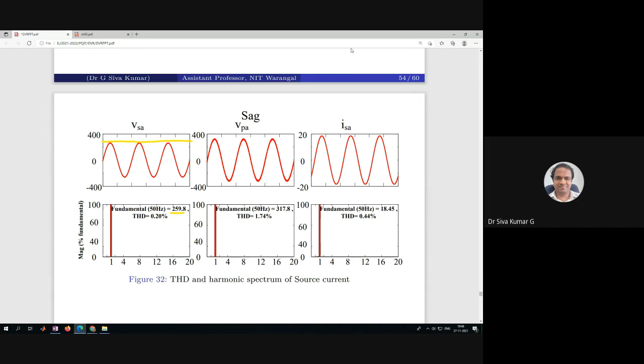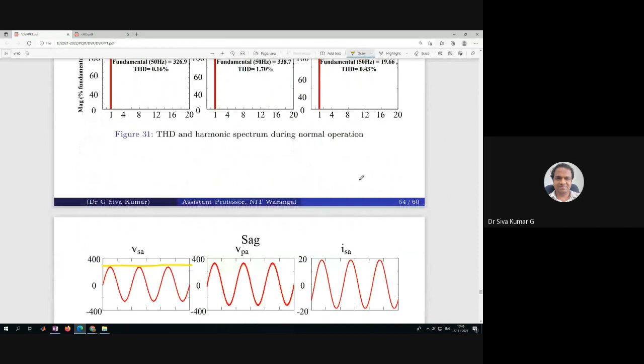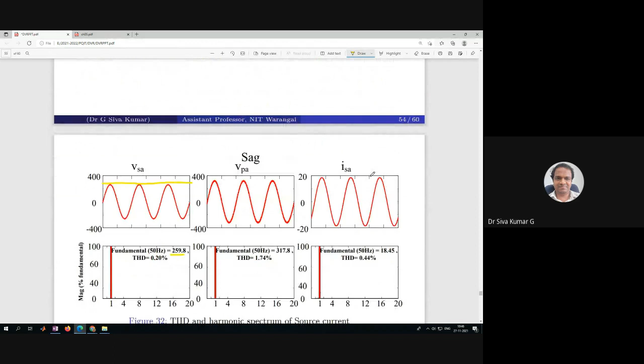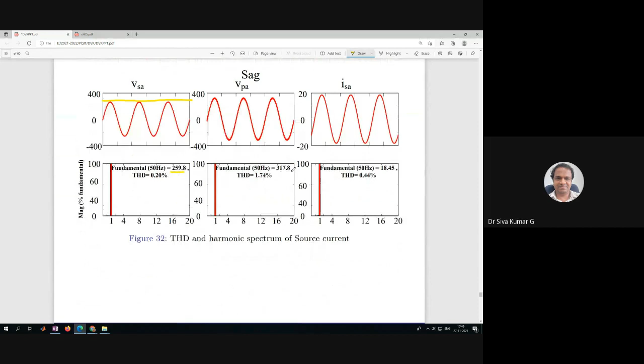It does not reach exactly the value which was expected, 320, 340, but somewhere the drop is much higher when you keep the reference voltage at 338. What we have achieved is 317.8, and the load current is 18.4. And in the swell condition, it is 394. This is a swell voltage. In that case also we are able to compensate the voltage and bring it back to 355.6, and your current is 20.6.